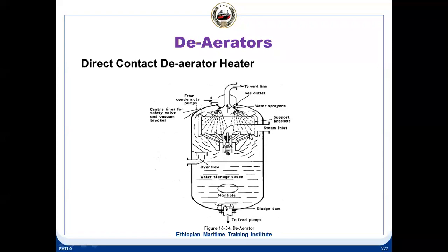If we put this cold condensate back into the boiler, the boiler first has to raise the temperature to 100 degrees centigrade and beyond before it starts evaporating and again becomes steam. To prevent all that waste of energy, we have a deaerating-cum-preheating of the condensate.